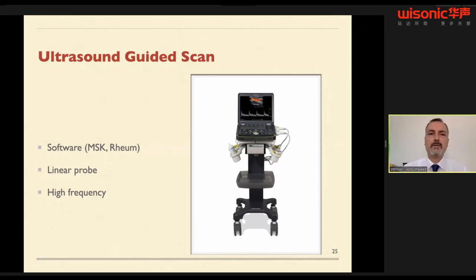It's not costly for the patient, with no risk of radiation or fear of the MRI tube. But the ultrasound machine should be a proper system with proper software for the knee joint scan, because each ultrasound machine has its own job. For example, an ultrasound machine for gynecology and obstetrics cannot be used for the knee joint or musculoskeletal unless it has a proper, specific software for musculoskeletal.